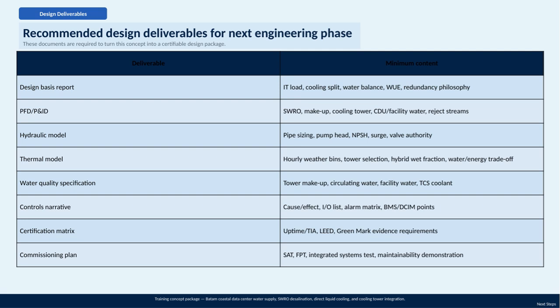Now, looking at the table, let's break down each deliverable and its minimum content. The design basis report should cover the IT load demands, how cooling loads are split, water balance calculations, water use efficiency, and our redundancy philosophy to ensure reliability. Next, the PFDs and P&IDs must detail the seawater reverse osmosis system, makeup water supplies, cooling towers, cooling distribution units, and all reject streams to fully map out the fluid flows. The hydraulic model will validate pipe sizing, pump head requirements, net positive suction head, surge conditions, and valve authority, which are all critical to system stability and efficiency.